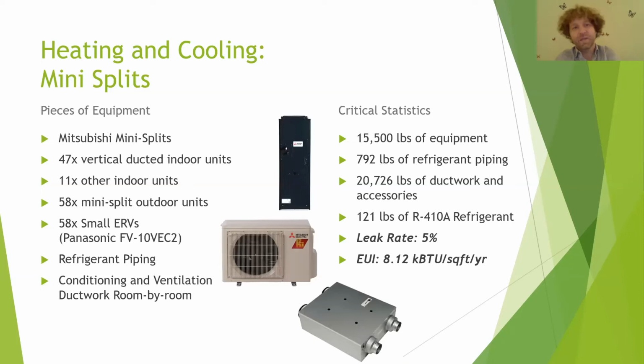The second system is mini splits, and so we went through and figured out exactly what the system would look like, how much refrigerant piping was in it, how much refrigerant is in it, and the leak rate on a mini split system is a little bit less because each unit has only one line set. So if anything does leak, it's only in one system. You have a little bit less leak rate and less than half the refrigerant in the piping.